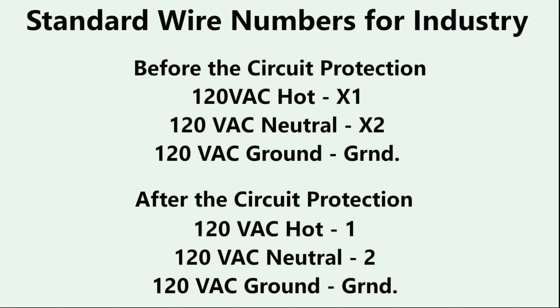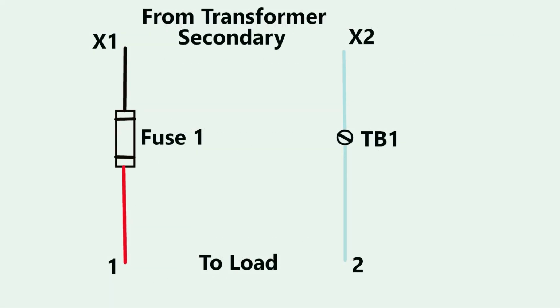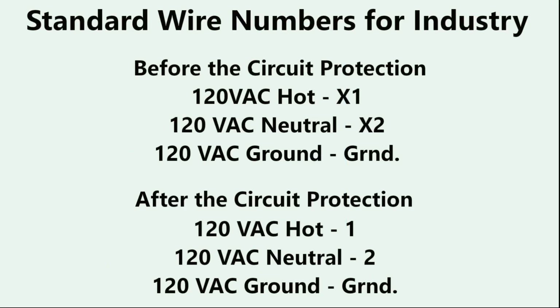Okay, now once you've dropped that voltage down, like if it comes in as X1 and X2 from a transformer, the wires that leave the transformer are called X1 and X2. After you go through a circuit breaker or a fuse or whatever circuit protection you've got, the 120 volt hot becomes 1, the 120 volt neutral becomes 2, and 120 volt ground remains ground.